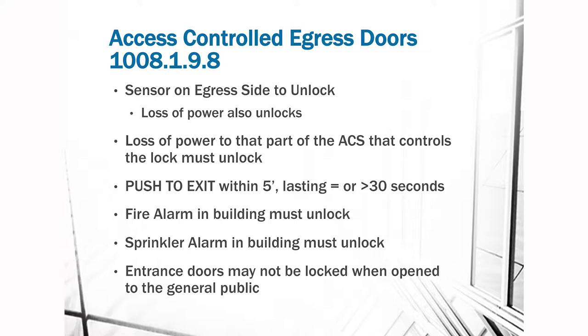Push to exit within five feet of the door — and it must last at least 30 seconds, though it can last longer. Fire alarm in the building, sprinkler in the building must unlock entrance doors. The door may not be locked when open to the general public — the entrance door to the building or an entrance door to a suite.